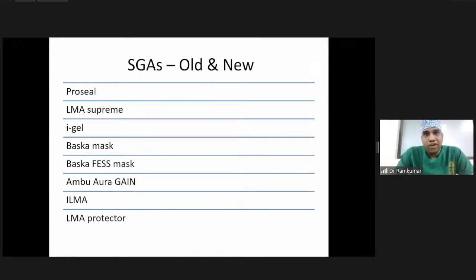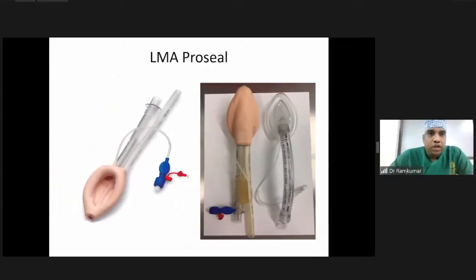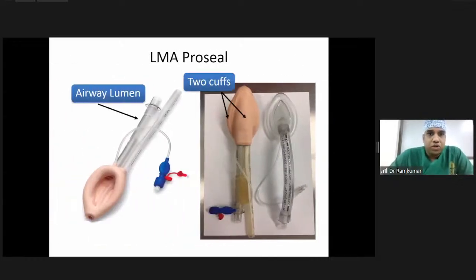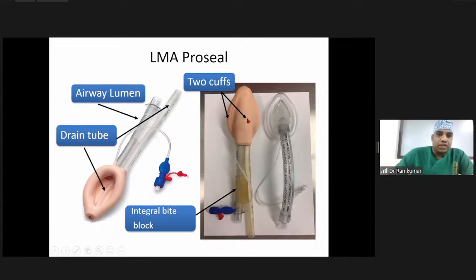From now on, we're going to see some of the important safety features or unique features of the commonly available devices in our part of the country. The devices which you're going to see are ProSeal, LMA Supreme, i-gel, Baska mask and Baska FESS mask, Ambu AuraGain, ILMA and LMA Protector. First is the ProSeal, which has 2 tubes. One is the airway tube. This is the anterior cuff, this is the posterior or dorsal cuff. And next is the drain tube, which runs in the posterior part of the cuff bowl and ends at the tip of the mask. This tube prevents epiglottic obstruction, the epiglottis blocking the ventilation. It is almost equivalent to an epiglottic aperture bar or an epiglottic elevating bar in the other devices.